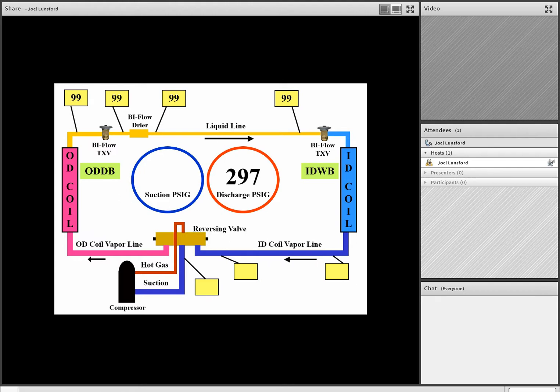In our next example, we see we have a refrigeration circuit. We have a heat pump. We're still in the cooling mode of operation, but it's a 410A heat pump. We see that we've changed the color of the background of our gauges.